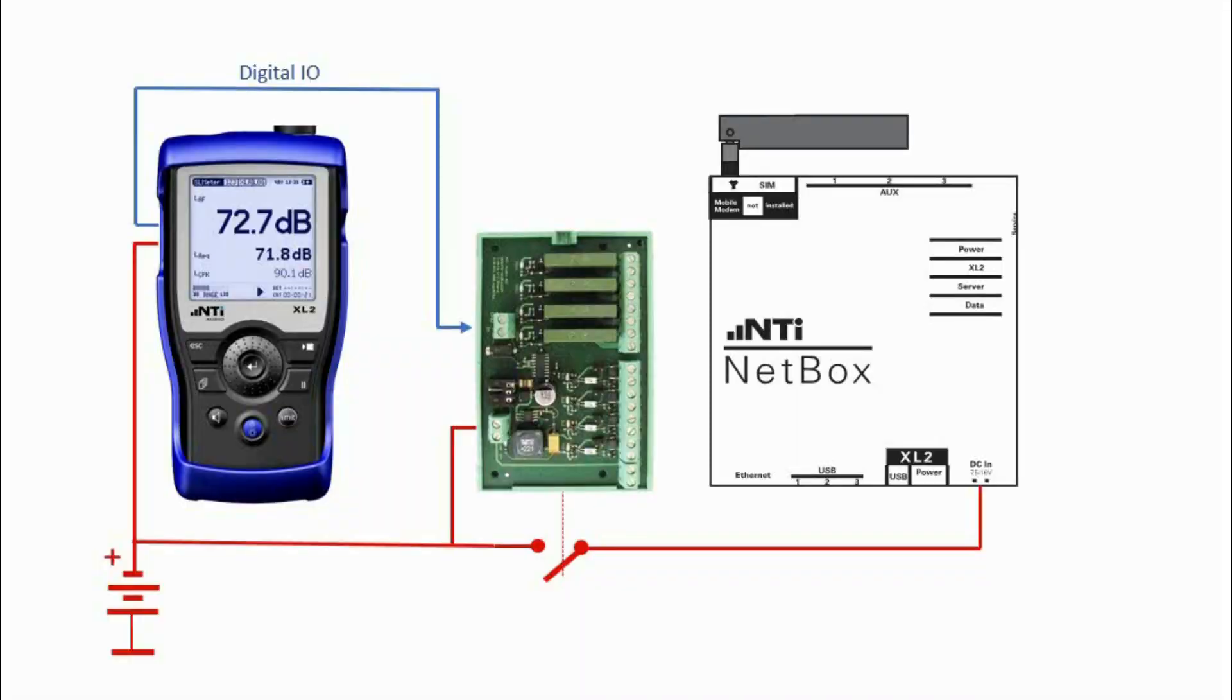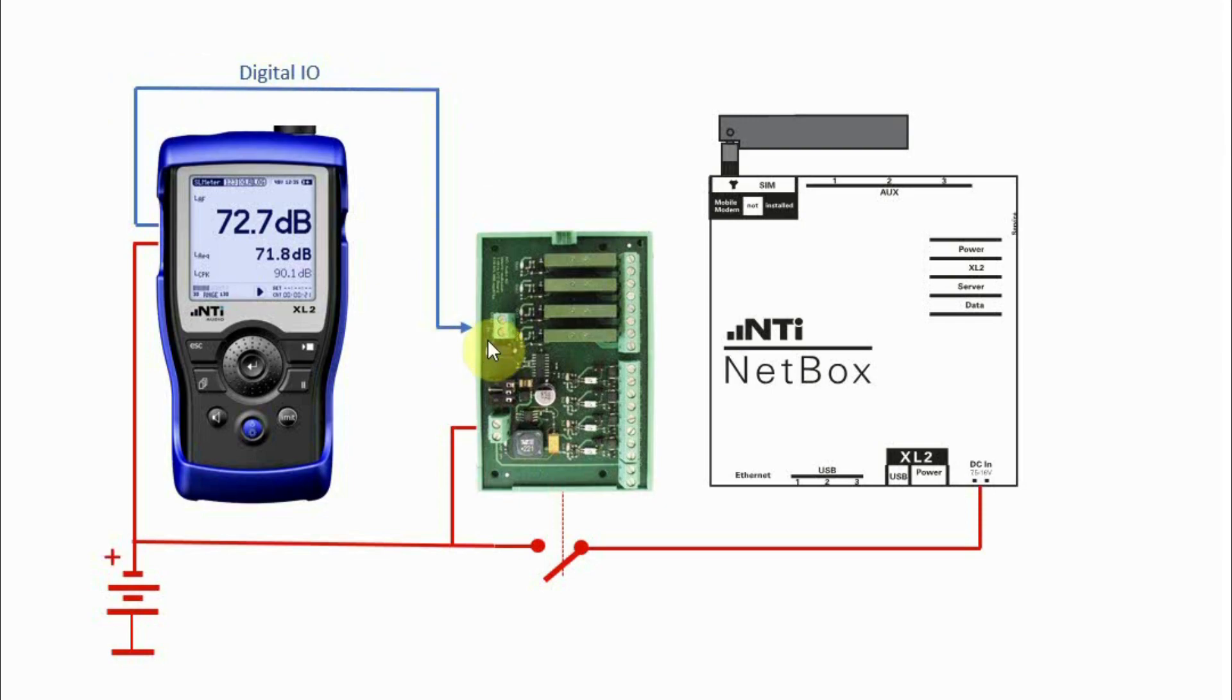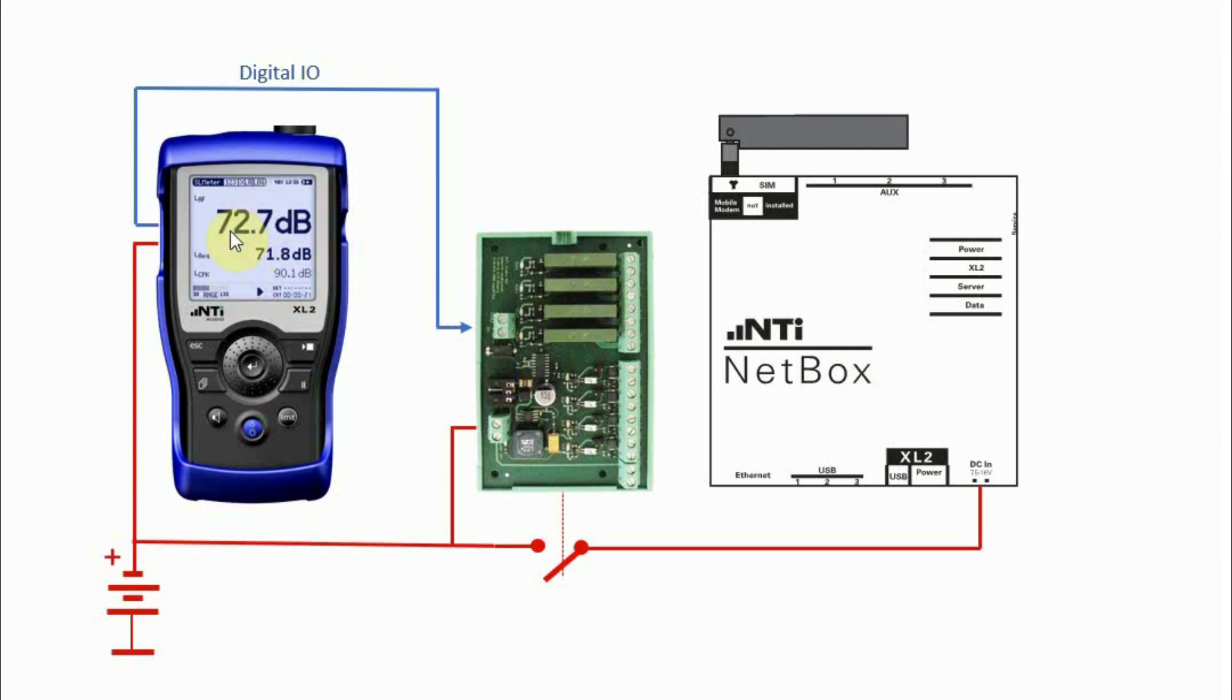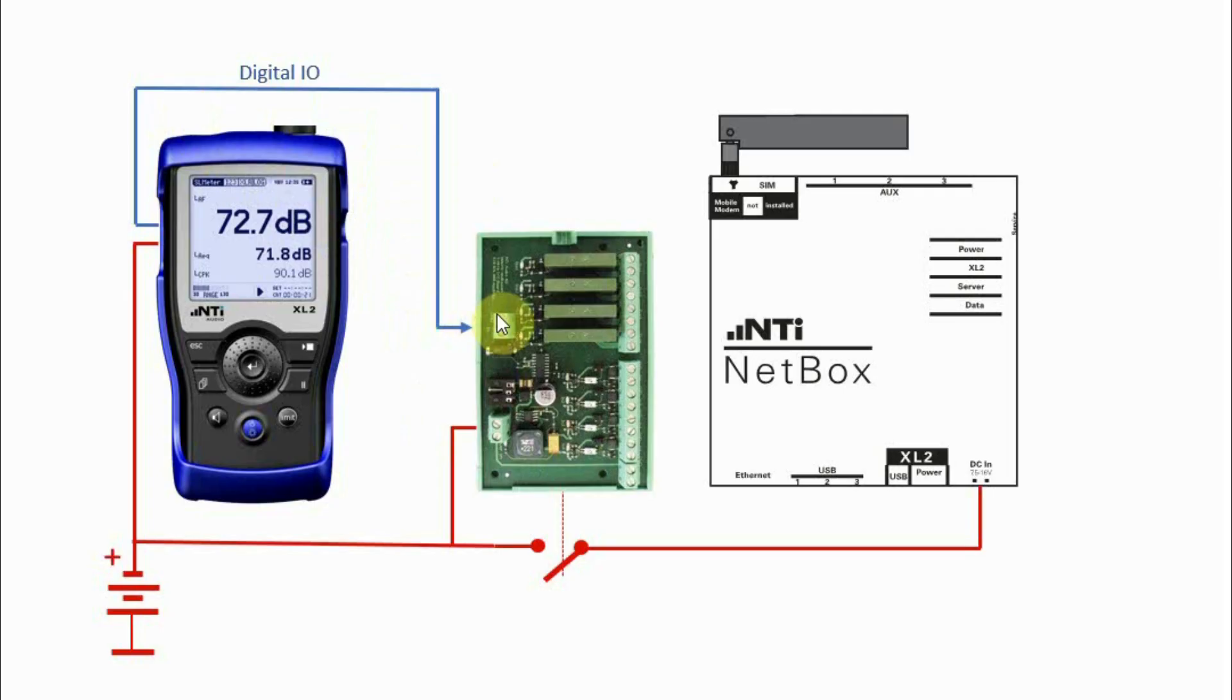With this flag set, the XL2 sends a command via the digital I.O. to the connected I.O. board. This command opens a switch that disconnects the power supply to the netbox and puts this device to sleep. After this, the XL2 itself also goes into the idle mode where only the real-time clock remains active and consumes only a few microamps. After the wake-up time arrives, the XL2 switches itself on and activates the digital I.O., sending a command to activate and close this switch again and that supplies the netbox and reboots the netbox.